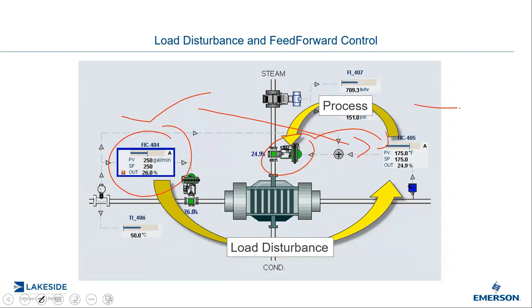The way you do that is to perform a load disturbance. You put the temperature controller in manual mode - there are a couple of different ways, but this is one of them - and change the product flow. You can see here I changed the product flow, and this is the output of the control valve that controls it. And you can see here, the temperature decreased.